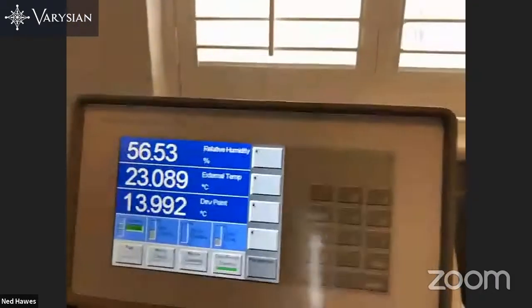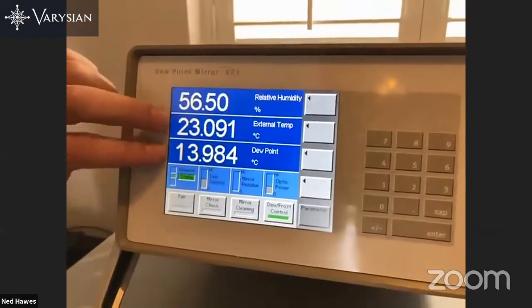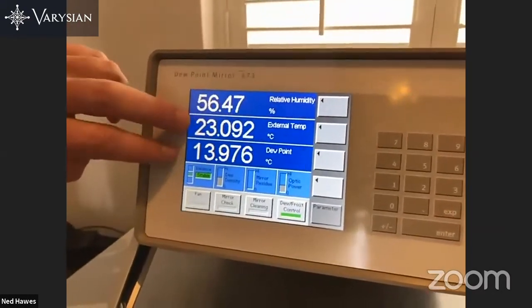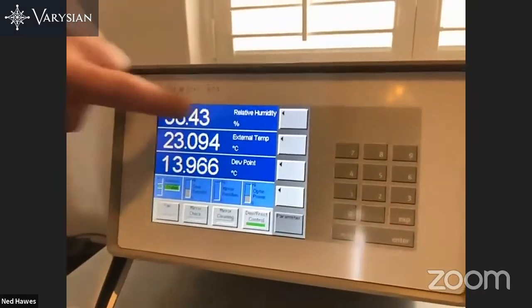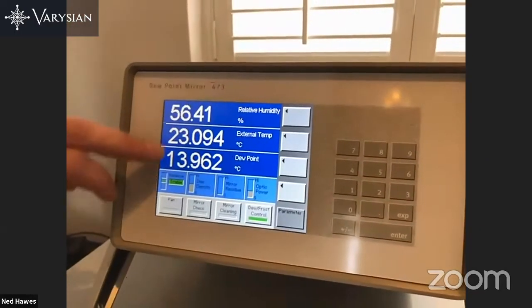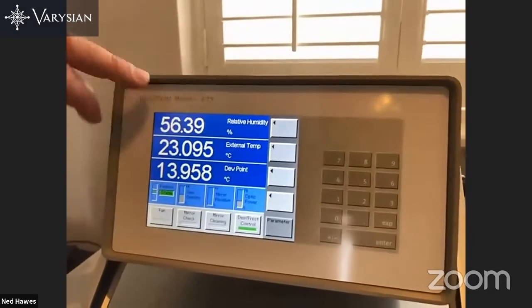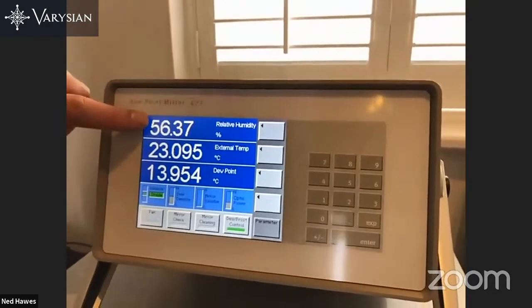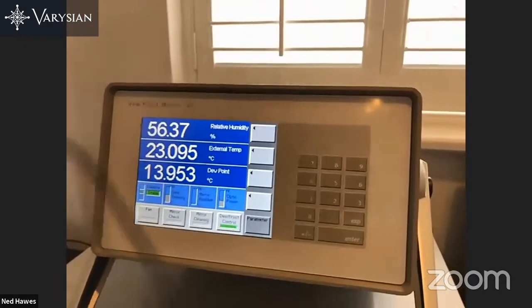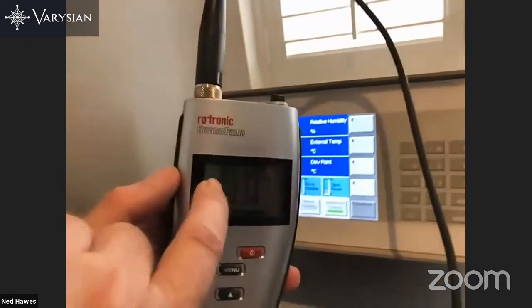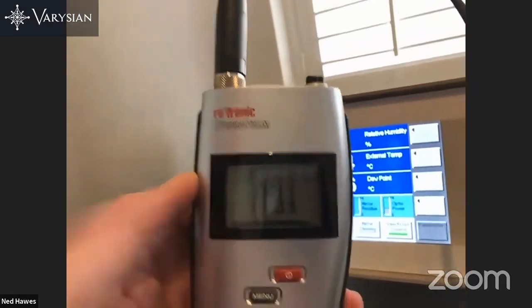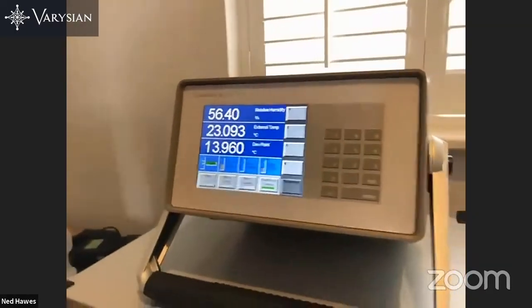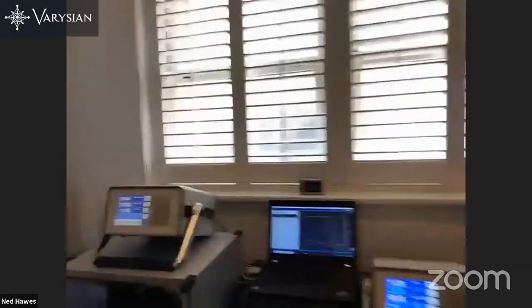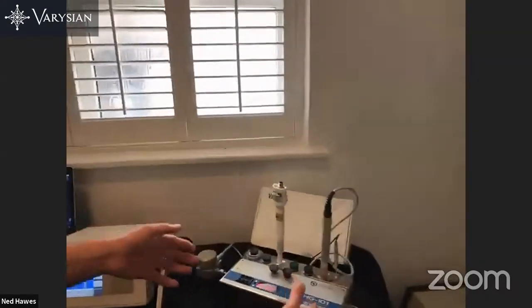Notice it's measuring a dew point and it's measuring the temperature. Those two temperatures are used to calculate the relative humidity. These are very accurate numbers, and from them you get a very good number for the RH, which you compare against what the instrument under test reads. Very similarly, we have the Fensel system here. These are your instruments under test.